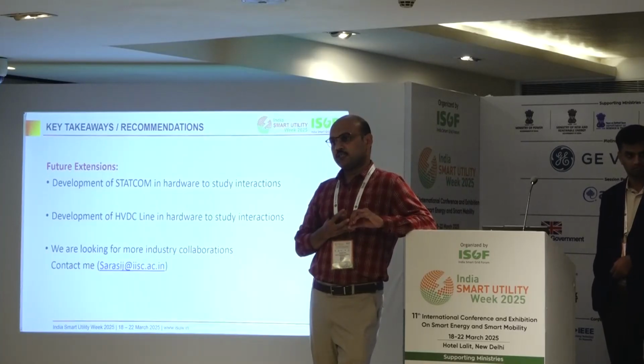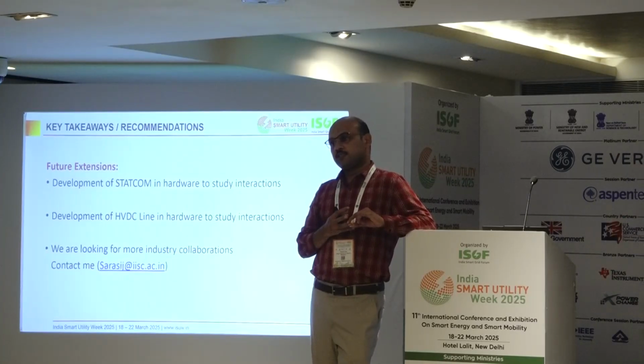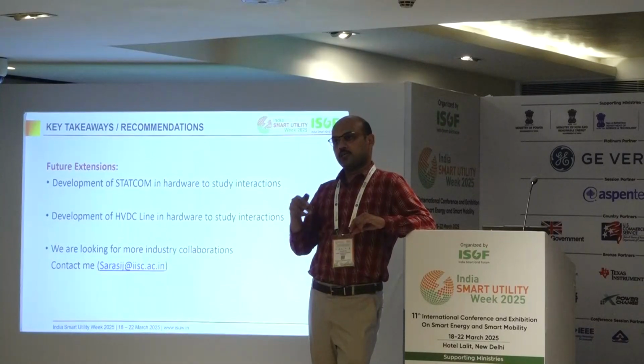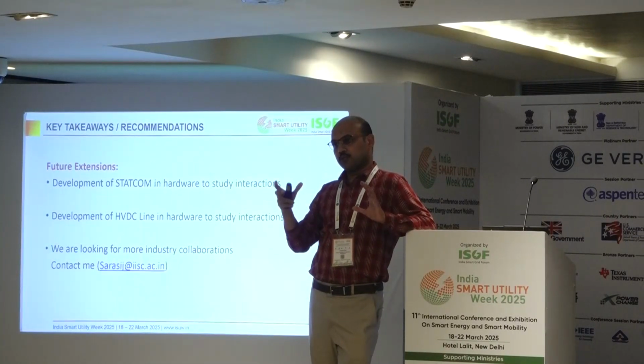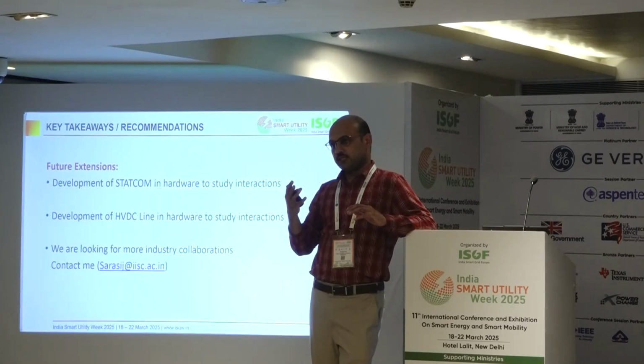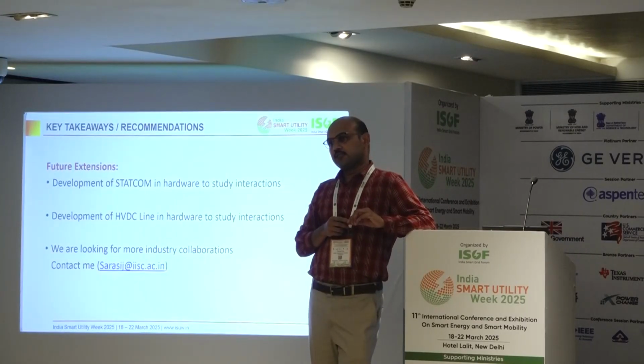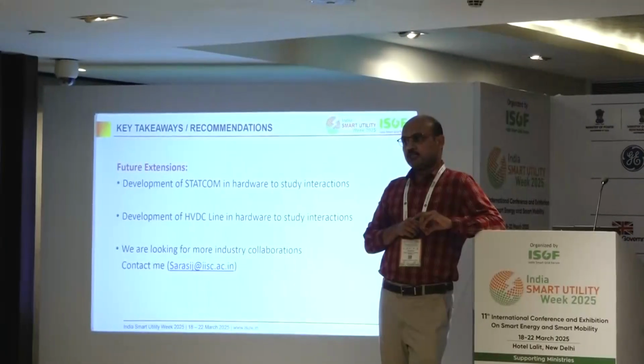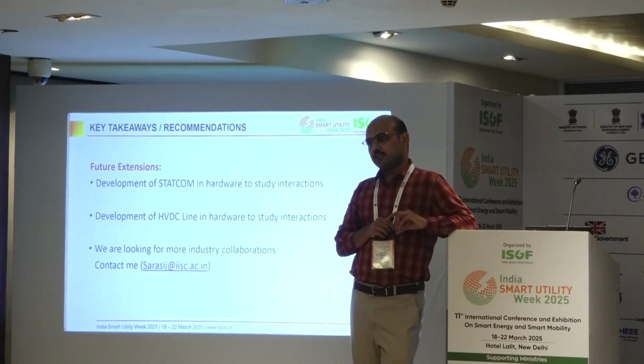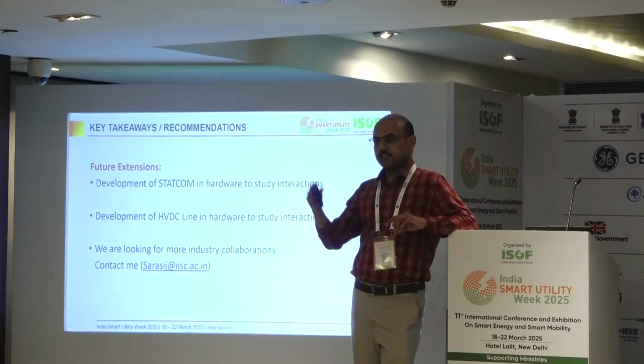For grid following, did you basically turn off volt-var control? No, there also you can keep it. Are you referring to the group control as volt-var control? In the GFL, the grid-dependent power logic, it's a question of how you tune your volt-var control support and the ranges you allow it to operate in - and that will differ between grid following and grid forming. So how - can the range be similar? Range can be similar, those are the questions that need to be answered.